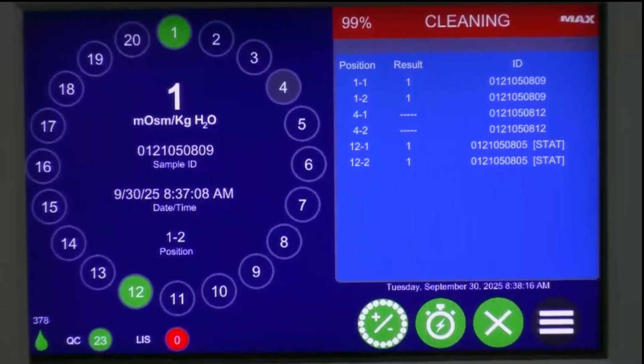We've upgraded the surfactant in that system fluid, so it maintains a much cleaner fluidic path without any user intervention at all. Moving forward, if you order this instrument, you're going to get a new lot of the OsmoPRO MAX maintenance kit with the reformulated system fluid, meaning you will not have to run enzymatic cleaner every day. You only have to run it every 500 tests as part of the 500 test maintenance process. Sorry, I got really excited because that's an announcement going out today, and we've been working really hard on it ever since launching the instrument.